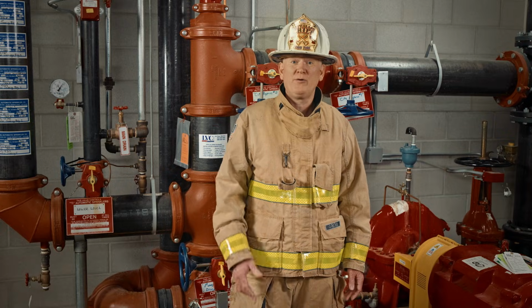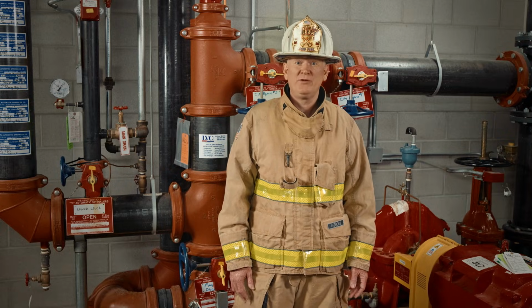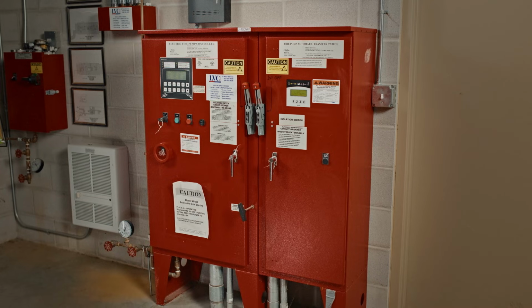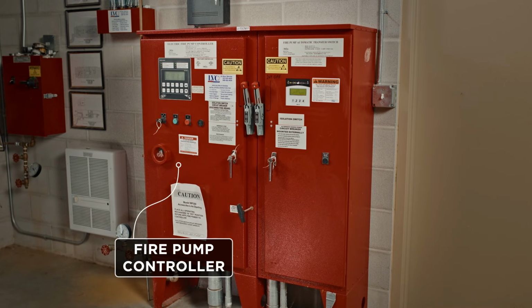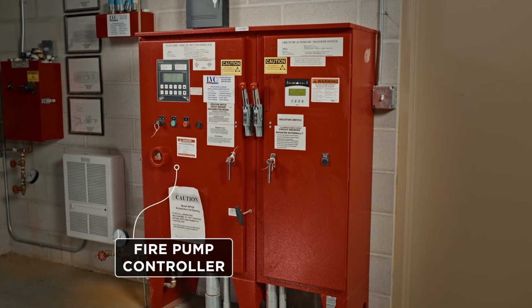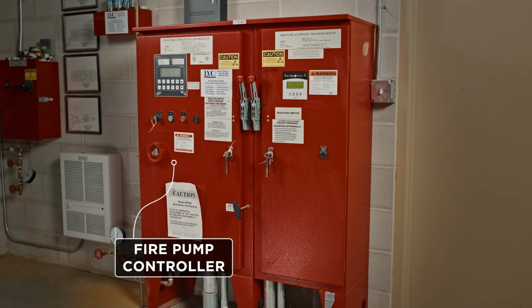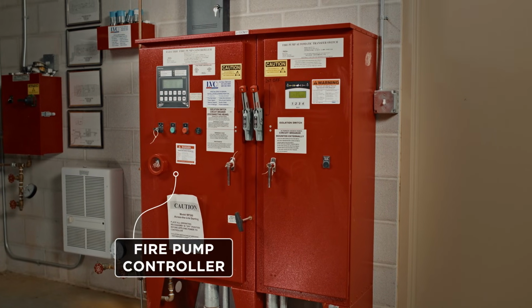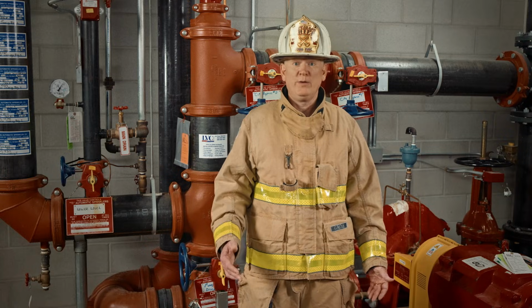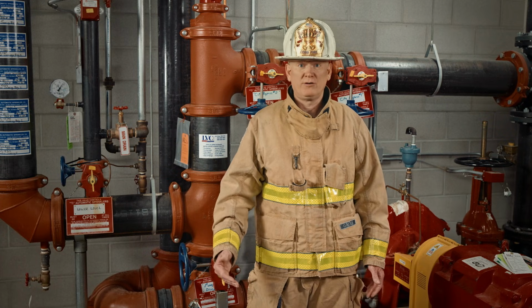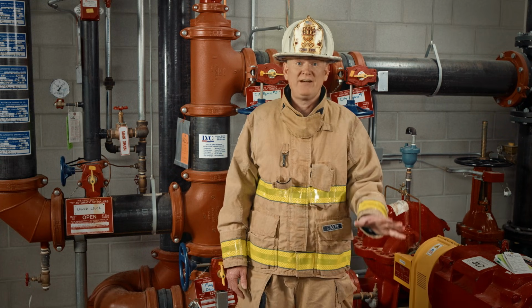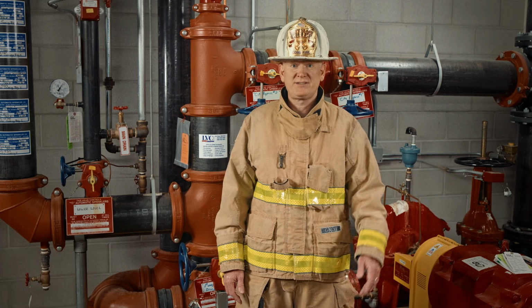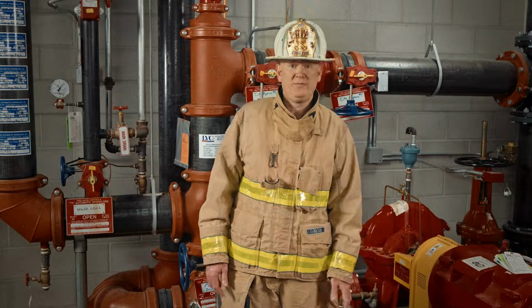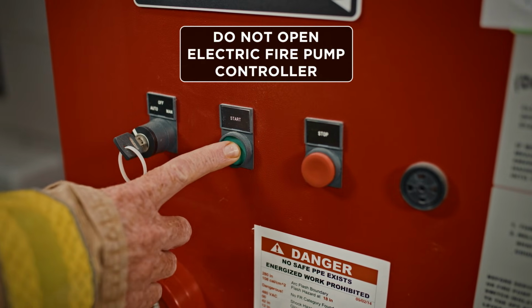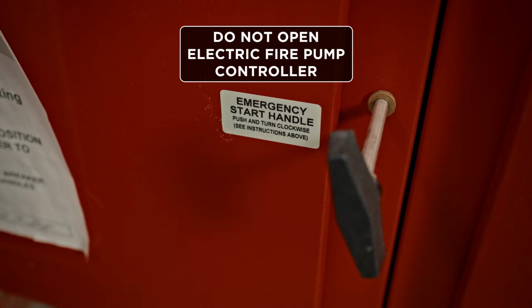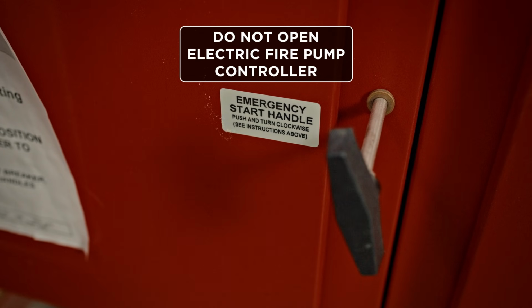The other component we want to identify in the fire pump room is the fire pump controller. Those are going to be the large red boxes on the side of the wall that are used to control the automatic and manual function of the fire pump. Do not open an electric fire pump controller. They have extremely high voltage inside, they are dangerous, and there is no need to open them. All of the manual and automatic functions can be controlled with the control box closed.